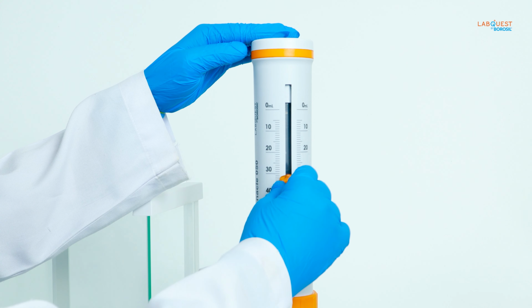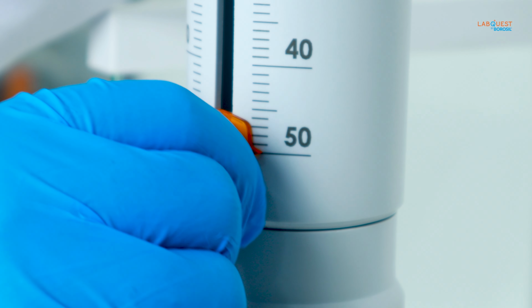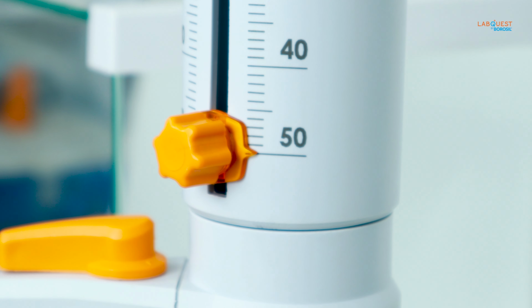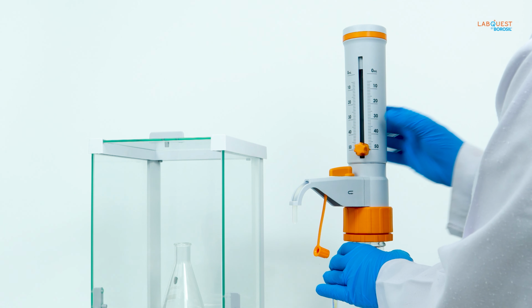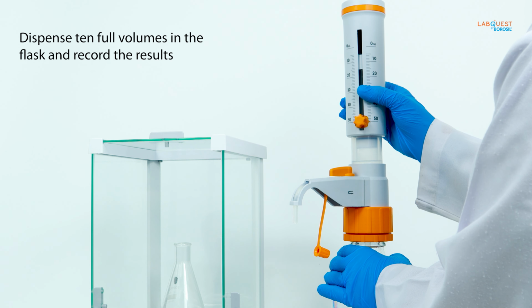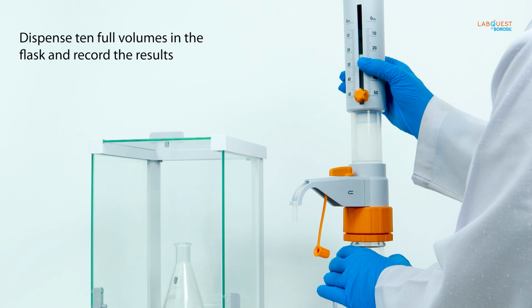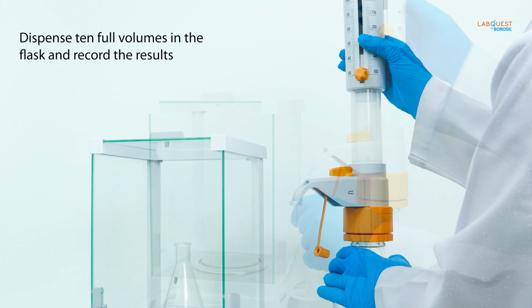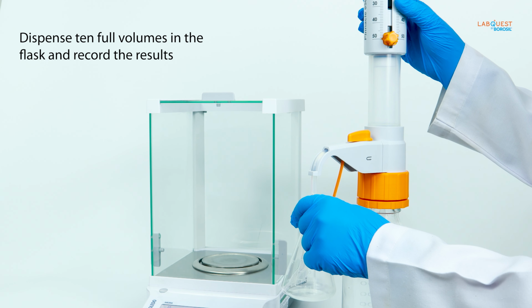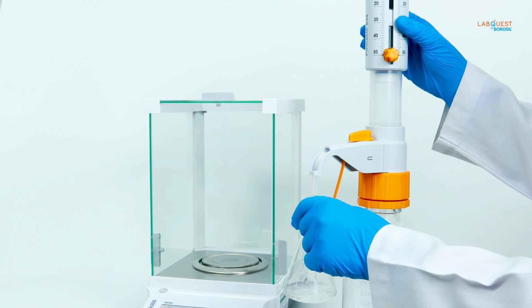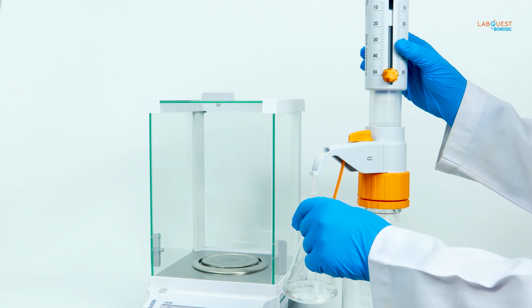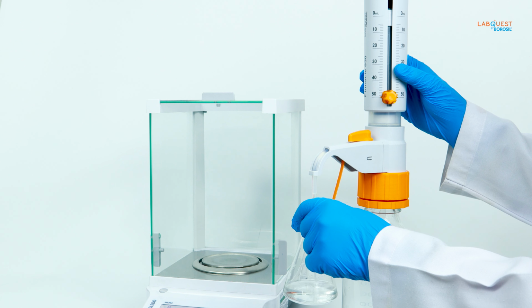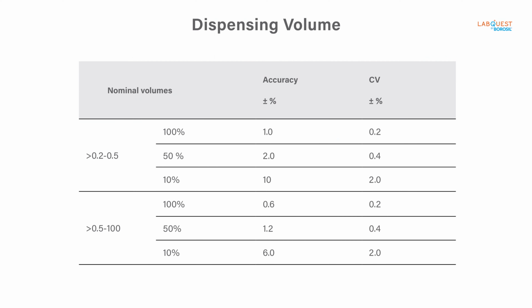Adjust the knob to select the volume you want to dispense, which is 50 milliliters in this instance. Dispense 10 full volumes of distilled or deionized water at different volume ranges, as recommended in the table, onto an electronic balance in the flask and record the results in the test record sheet.